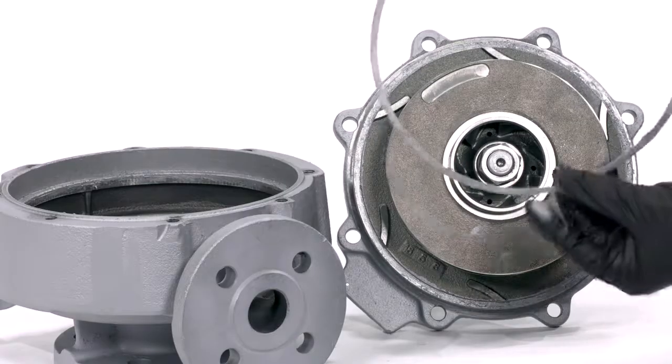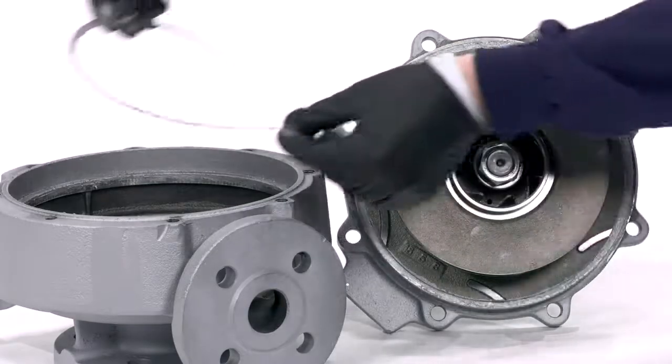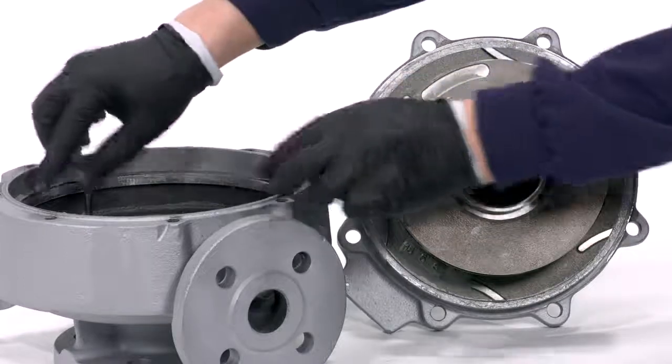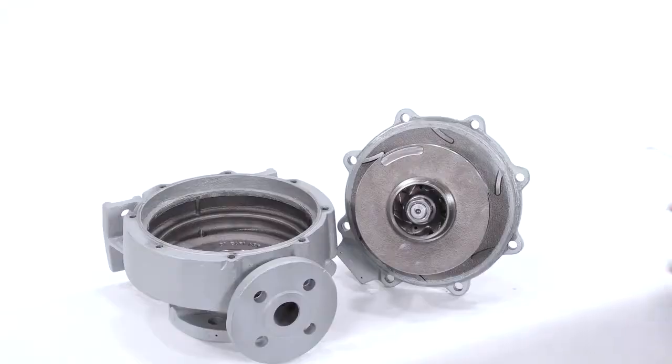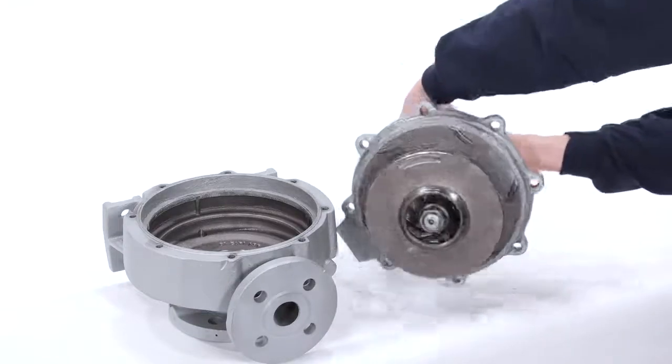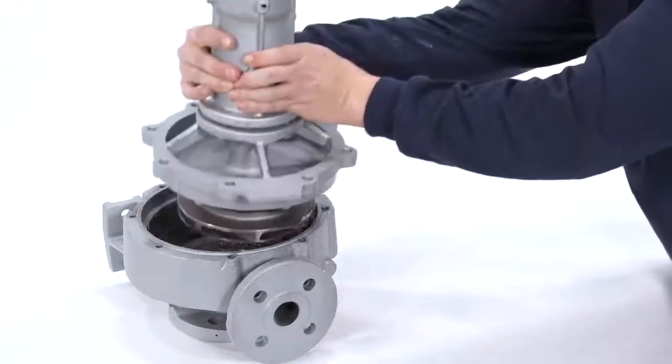Put the graphite laminated case gasket into the casing. Install the cartridge unit into the pump casing and tighten the eight casing bolts with a 17mm wrench.